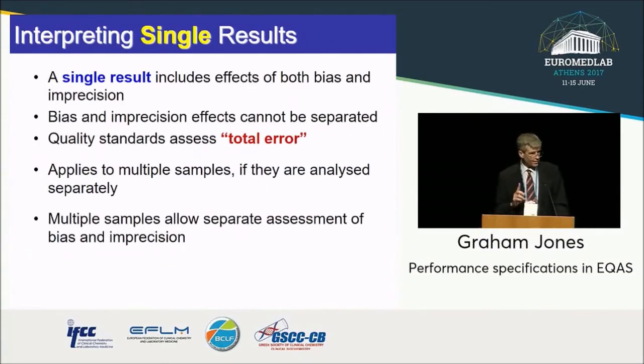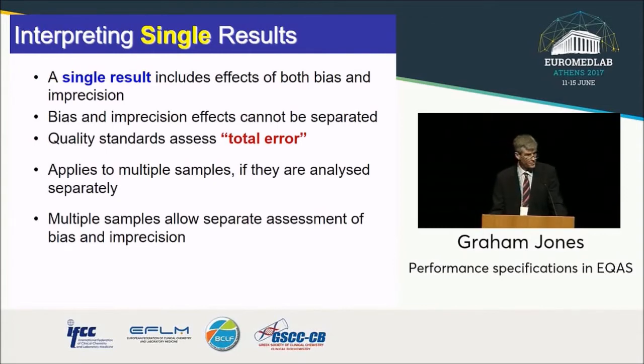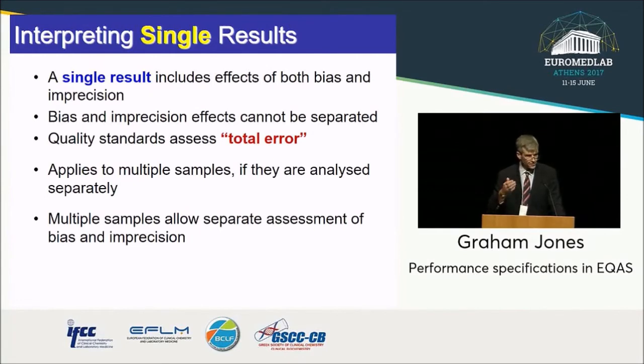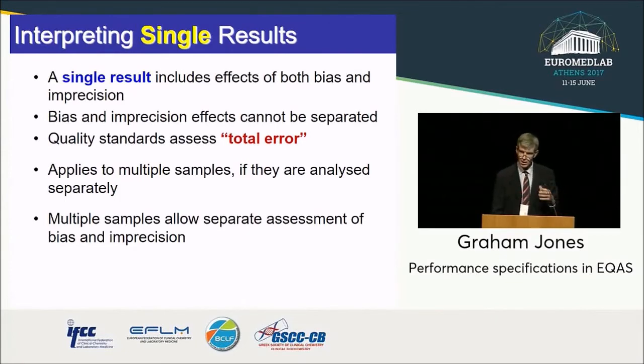A patient gets one result, and often EQA is the same — a single result includes the uncertainties or errors of everything that's gone into it: bias, imprecision, analytical specificity issues — combined into what we can call total error or total uncertainty. Therefore, if we want to put a performance standard against it, we need one against a single result that encompasses all of those factors. They may be traded off against each other, but it's a single set of results. Once you have multiple samples, then you can tease out the separate subparts — whether there is bias, imprecision, and how large they are.